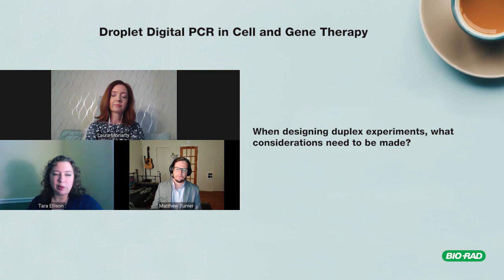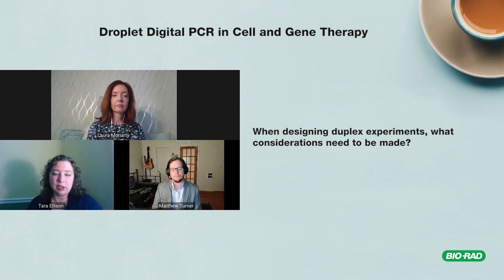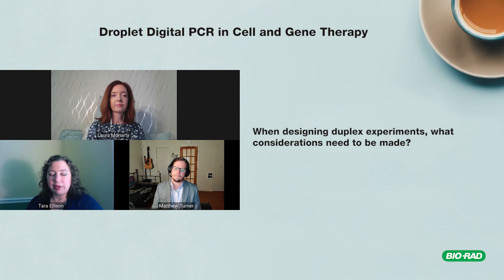Since ddPCR is an endpoint reaction, we don't measure every cycle like in qPCR — we wait until the end, make droplets, do PCR to endpoint, then read droplet fluorescence. Efficiency doesn't matter as much as long as it's good enough. Bio-Rad has a two-color instrument, the QX200 — channel one is FAM, channel two uses HEX or VIC. The newly launched QX1 can read four channels.